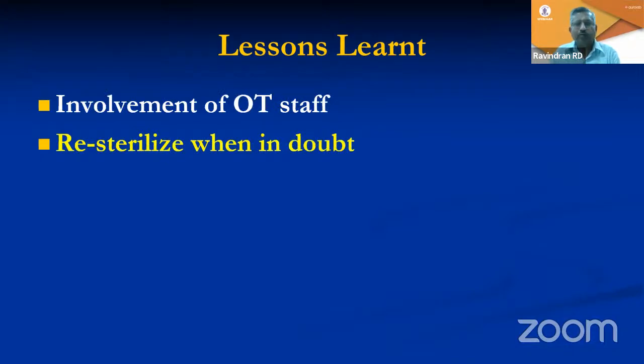The second is the involvement of the OT staff. On the particular day when this incident happened, the staff were not very happy about the bin. When a set of instruments has undergone a full cycle of autoclaving, they really have the feel of the towel and the instruments, all of that, which was missing in this case, even though the sterilization marks were appropriate. Because of the assurance given by the CSSD staff, they autoclaved it. From that point, any doubt we have, we resort to re-sterilization. At least I personally did, on 3 or 4 occasions where we had a doubt. We were not very sure because the printout was not clear, or one indicator had not changed, so we re-sterilized it.